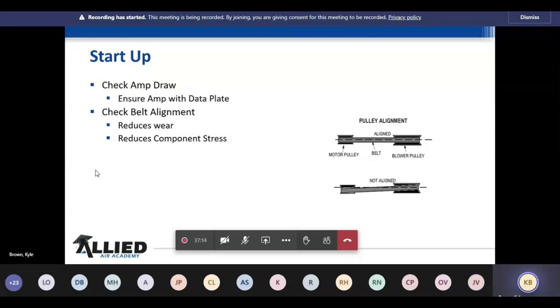Now, the previous slide showed us it's pretty easy to line the belt up. You can look straight in at it. On your bigger units, you're going to have a different blower configuration, and you may have to measure from blower housing to the belt, or a known common platform on the backside, to make sure you've got the same length from back to front on both ends of that belt.